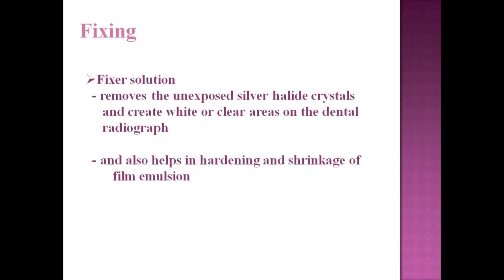After rinsing, the film is placed in the fixer solution. The fixer removes the unexposed silver halide crystals. If they are not removed, we cannot differentiate the exposed from the unexposed areas. The exposed areas are already dark; the unexposed silver halides create white or clear areas when removed, allowing us to see the structures on the x-ray. The fixer also hardens and shrinks the film emulsion.